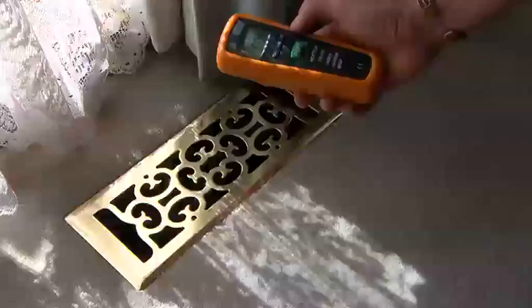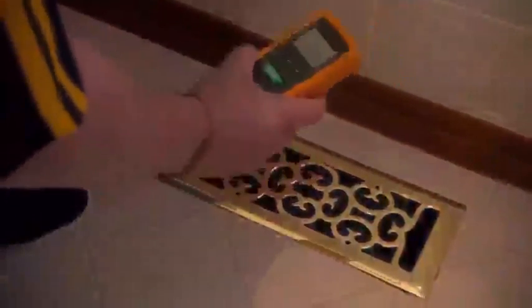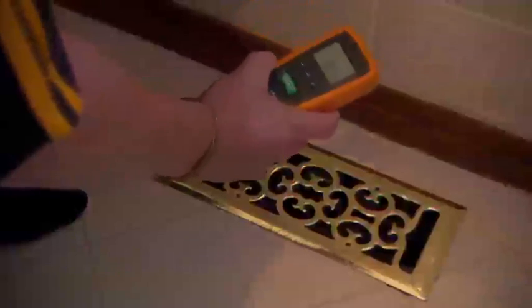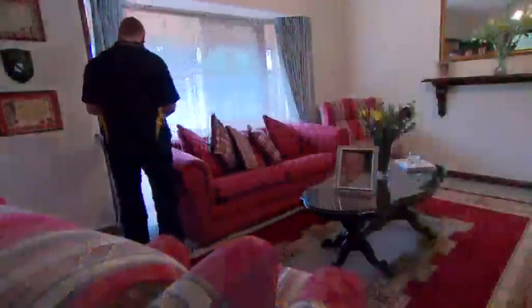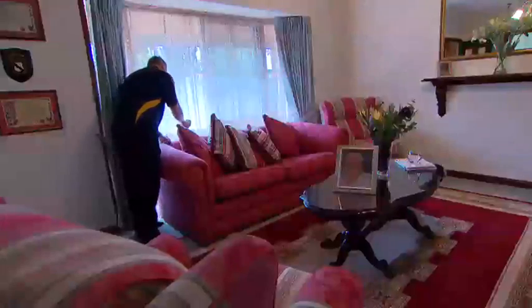If any cracks or openings within the heat exchanger of the central heater are present, combustion products that contain CO can be dispersed throughout the building. If CO readings are evident, they may only be minor initially. Please note, however, as the heat exchanger heats up and cracks and openings expand, more combustion products can enter the supply airstream and flow into the building. If the CO level exceeds the initial background levels, then the appliance is leaking or spilling CO.